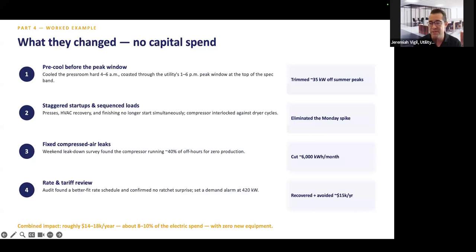The second thing you could do is demand management: staggering your startups and sequencing your load. We're not saying turn off everything, just don't turn it all on at the same time. You have your HVAC, presses, finishers, dryers, all these different cycles. If you turn everything on at once, that pulls more energy at one time, causing your demand to spike. If you eliminate that spike and stagger the loads a little, your utility bill will go down naturally.